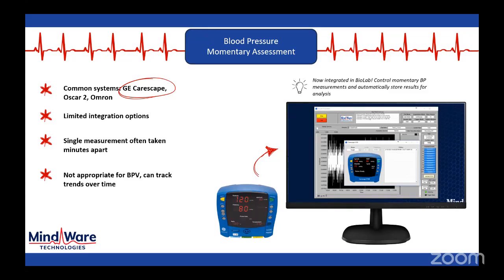And so there's a special cable that we've designed that connects between the CareScape device and the PC that is running BioLab. And with that, we're able to press buttons on this screen-based CareScape device, and they mimic the buttons that exist on the actual device. So if you press the green button, you can inflate the cuff and take a measurement. Those measurements are then stored as event markers in the file with all of the values of interest, systolic, diastolic, and mean arterial pressure. And then you can extract those later and do whatever you want with them, including doing something like a threat versus challenge assessment if you wanted to do that.